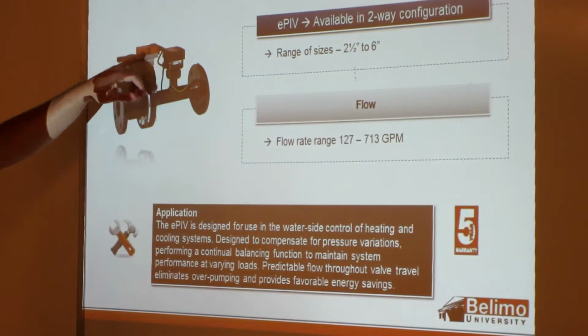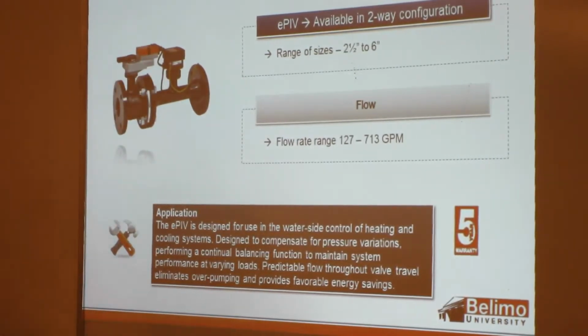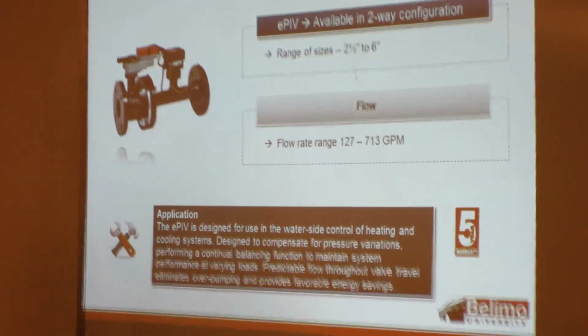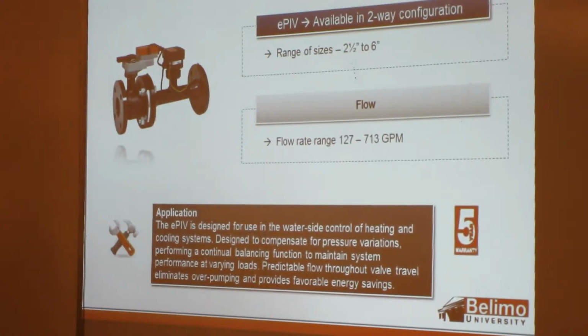So the magnetic flow sensor is tied into your actuator. Your actuator has a feedback wire, and the feedback that you get is a linear feedback. So say you've got your 2 to 10 volt feedback coming out, so 6 volts is 50% of that. If you're getting a 6 volt signal, say it's the 127 GPM 2.5 inch, you're going to be getting 50% of that, so 63.5 GPM will be going through that valve. So it alleviates the need to have any other kind of flow sensors on there if you're using this valve.